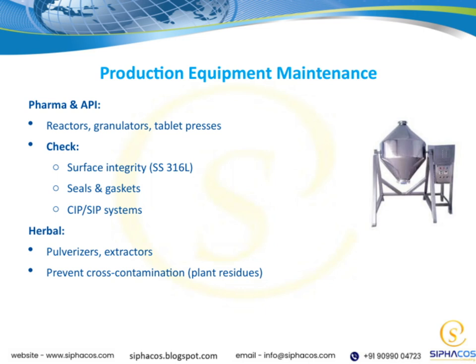When inspecting these pieces of equipment, I focus on surface integrity, especially since most are made from stainless steel, like SS316L. Keeping surfaces smooth and intact helps prevent contamination and makes cleaning easier. Seals and gaskets are also vital, they keep the system airtight and prevent leaks, so we always check for signs of wear or damage.